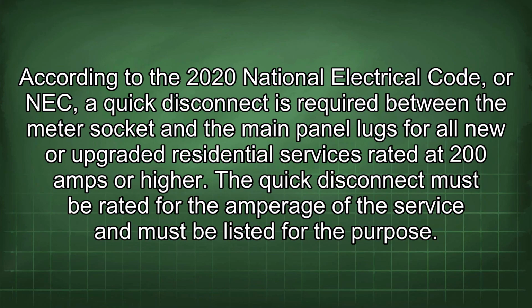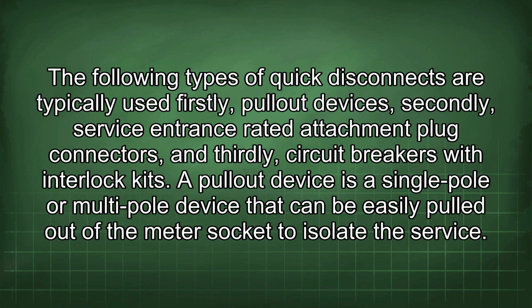According to the 2020 National Electrical Code, or NEC, a quick disconnect is required between the meter socket and the main panel lugs for all new or upgraded residential services rated at 200 amps or higher. The quick disconnect must be rated for the amperage of the service and must be listed for the purpose. The following types of quick disconnects are typically used: firstly, pullout devices; secondly, service entrance rated attachment plug connectors; and thirdly, circuit breakers with interlock kits.